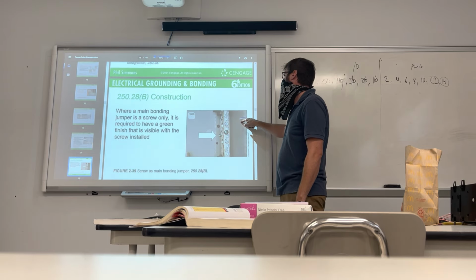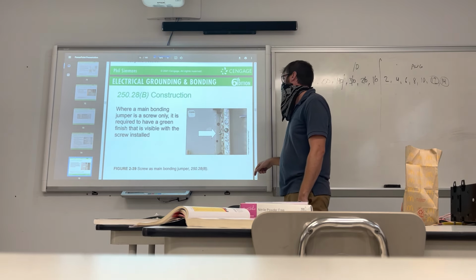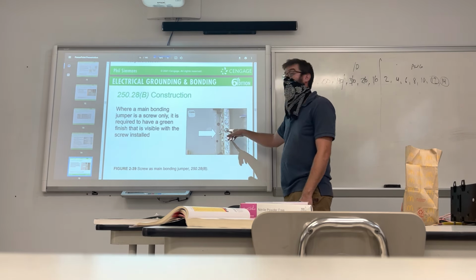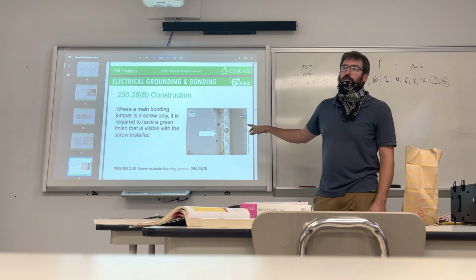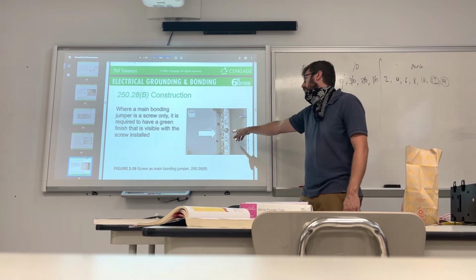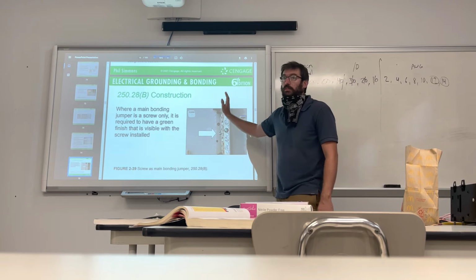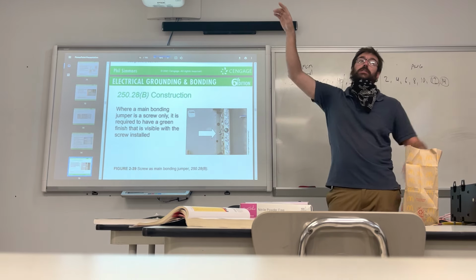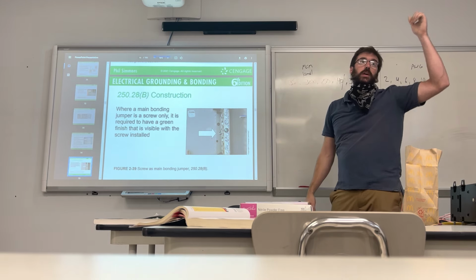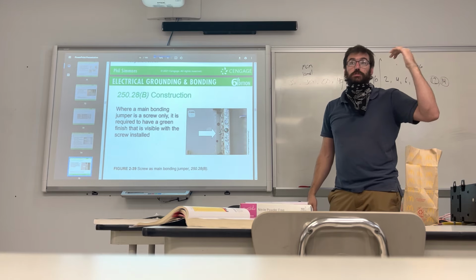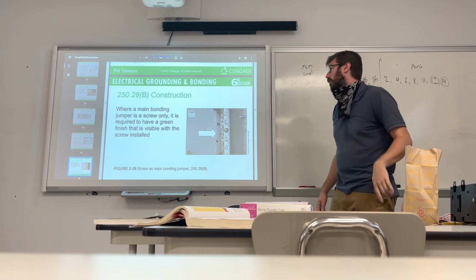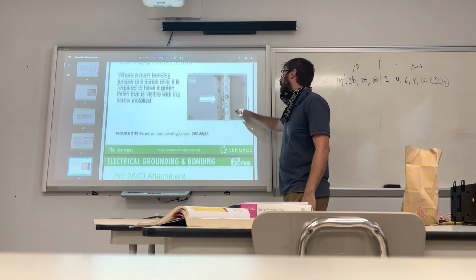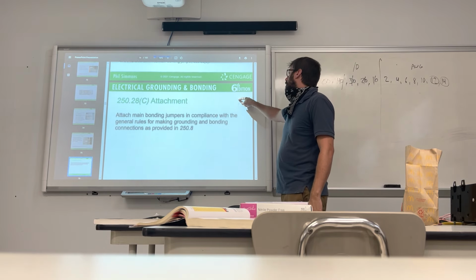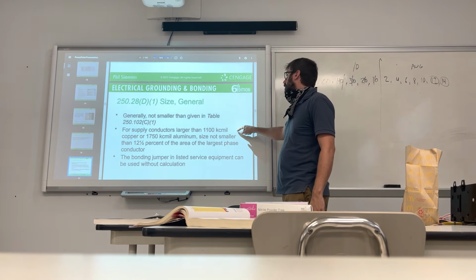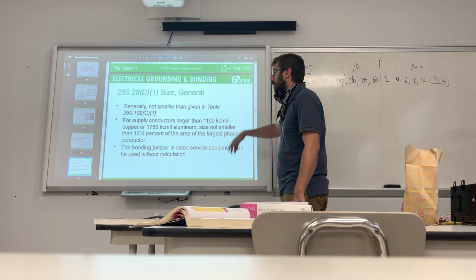And that's the screw that I was just mentioning. It looks just like that. I mean, not quite just like that, there's a couple different variations. Normally when you see that screw, it's not just in the middle of a panel box, it's usually on the top right or top left-hand corner of the service. And right where that neutral comes in, the screw is usually right below it in most modern panel boxes. All right, we're not gonna talk about this.